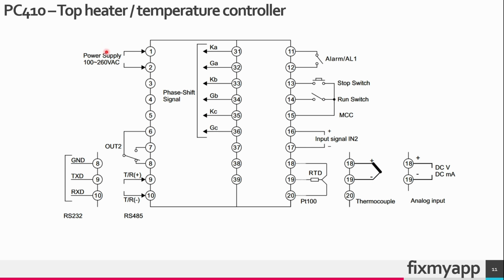The power supply will be connected to terminals 1 and 2. Terminals 4 and 5 will be the output of the solid state relay, and the solid state relay will drive the heating element of the top heater. When you start a program, the output on terminals 6 and 7 will be switched on. This will switch on the solid state relay of the bottom heater. Terminals 8, 9 and 10 will be used for the serial communication.